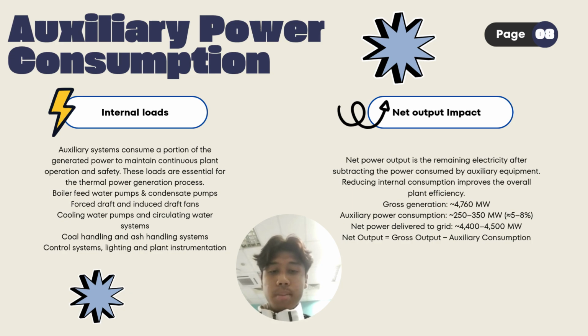For the net output impact, net power output is the remaining electricity after subtracting the power consumed by auxiliary equipment. Reducing internal consumption improves the overall plant efficiency. Gross generation is about 4,760 megawatt. Auxiliary power consumption is about 250 to 350 megawatt, about 5% to 8%. The net power delivered to grid is about 4,400 to 4,500 megawatt, and the net output is equal to gross output minus auxiliary consumption.